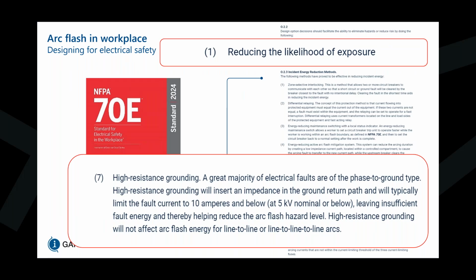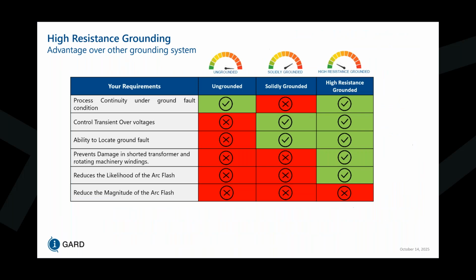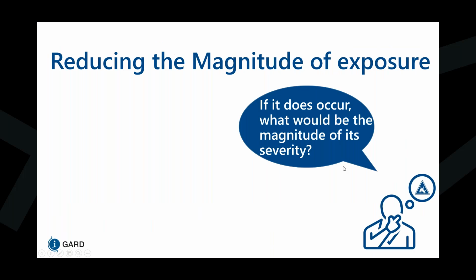So although HRG can reduce the likelihood of exposure for 95% of the cases being phase to ground faults, it's not able to do the remaining 5% when it comes to phase-to-phase or three-phase failures. So we need another incident energy reduction method to go alongside the good task that high resistance grounding is doing to cover the remaining 5%, where 95% is being covered by HRG and the remaining 5% can be covered by an arc flash sensor. So far, we know that the standard high resistance grounding unit is able to reduce the likelihood of arc flash, but by itself, it can't reduce the magnitude of an arc flash.